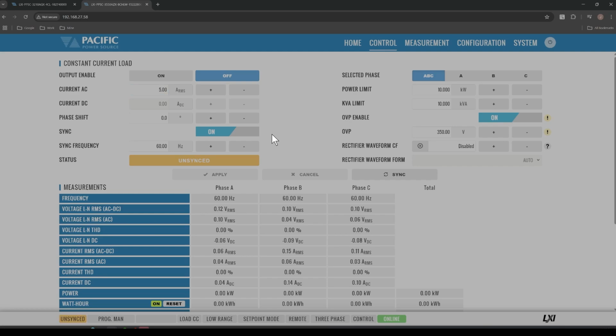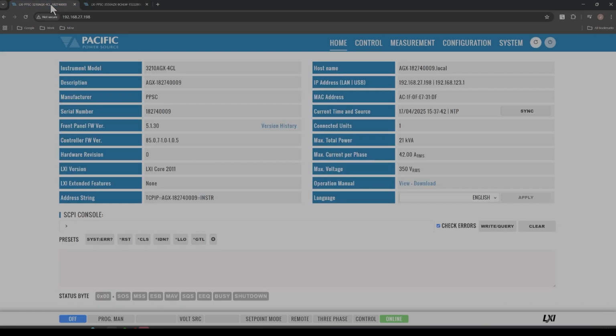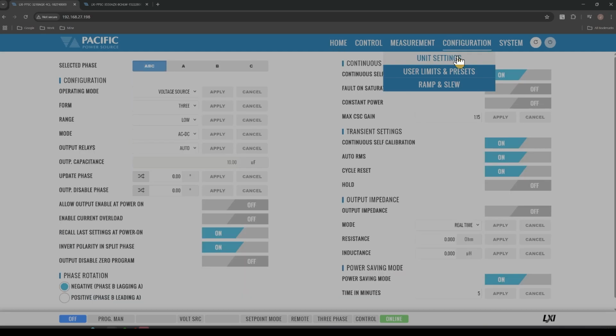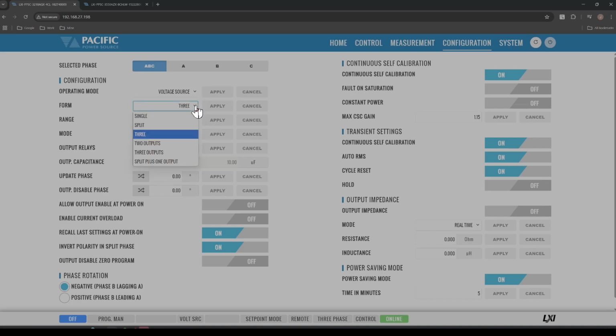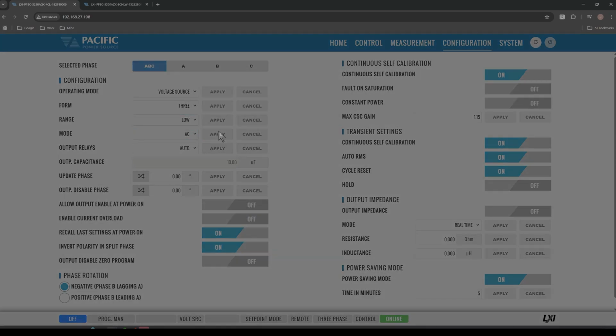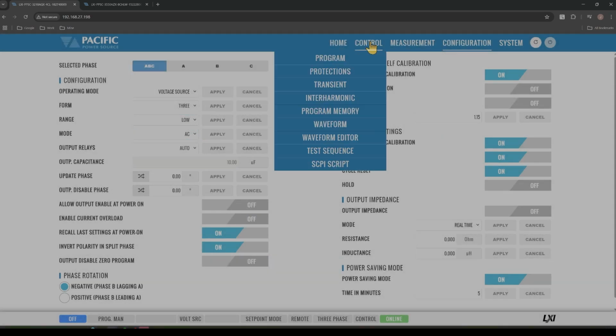I'm going to switch over to the 3210AGX, which is this window right here. Let's check the configuration, make sure it's set up how we need. The unit settings - this is already set up as our voltage source. We are in 3-phase mode, just like the load. Low range for voltage, AC mode.